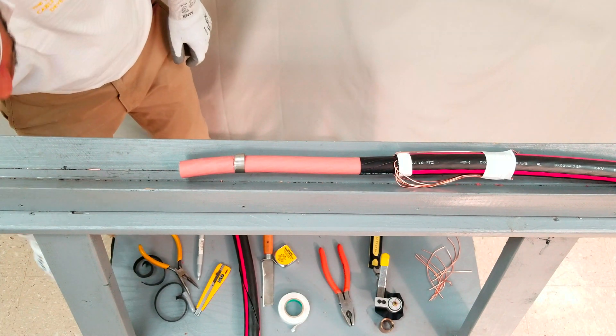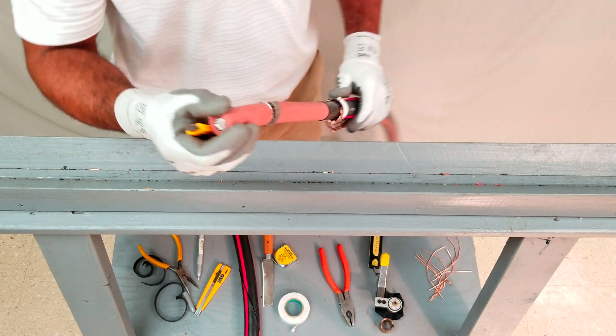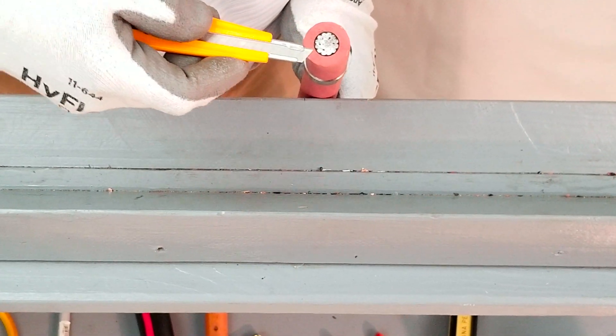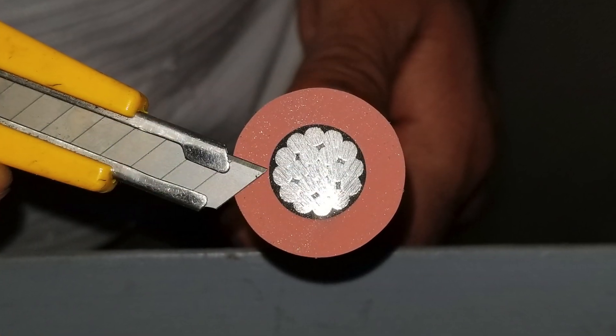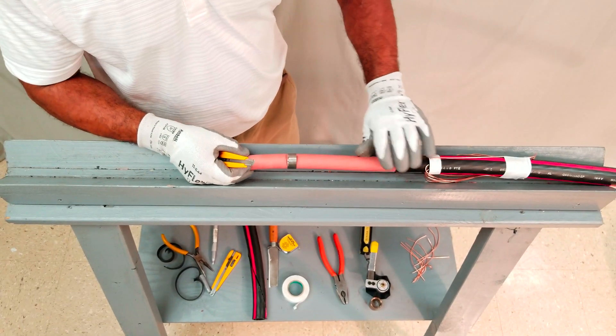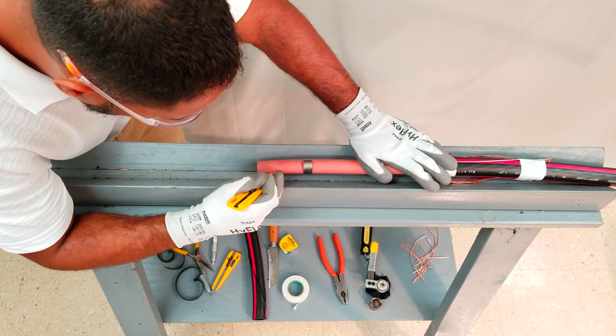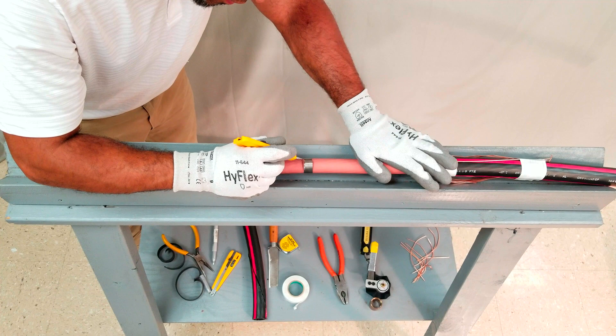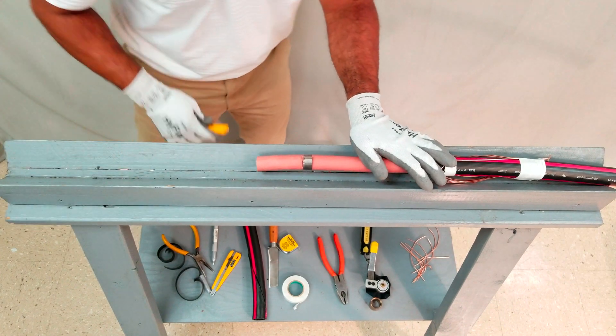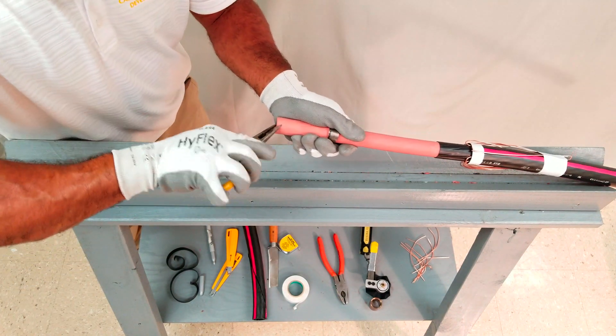Next, longitudinal cuts may be made from the insulation ring cut to the end of the cable to facilitate removal. The OLFA adjustable utility knife will be used to accomplish this. Holding the OLFA knife against the end of the cable, set the blade depth to approximately 95% of the insulation thickness. When the cuts are being made, be careful not to nick the underlying conductor. Needle-nose pliers or channel locks may then be used to remove the insulation piece from the conductor.